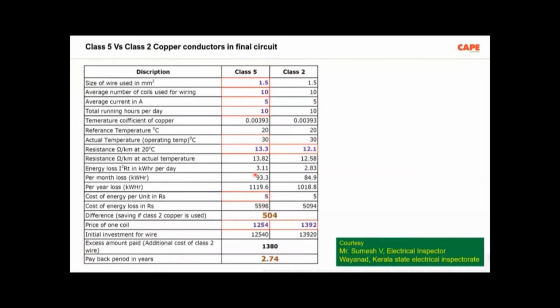In the final circuit, especially inside our houses, inside the small scale industries, or the low voltage final circuit wiring, or we use the word conduit wiring, we use copper wires in conduits, especially up to 10 square mm copper wires are recommended. Now, copper wires are available in two types of conductors, class 5 conductor and class 2 conductor. Class 5 conductor has a higher resistance. In comparison, class 2 has a lower resistance. The standards, be it IS standard or IEC standard or whatever the standards, always consider a class 2 conductor for calculation of different derating figures in an electrical installation.